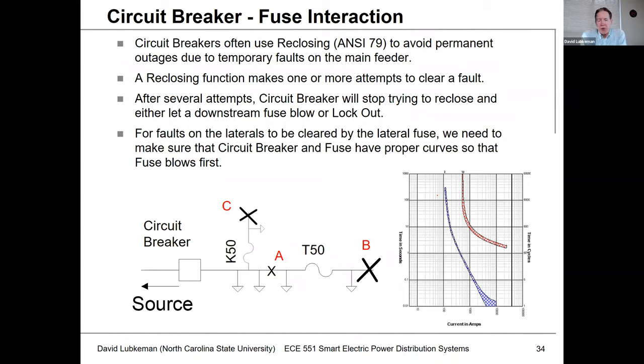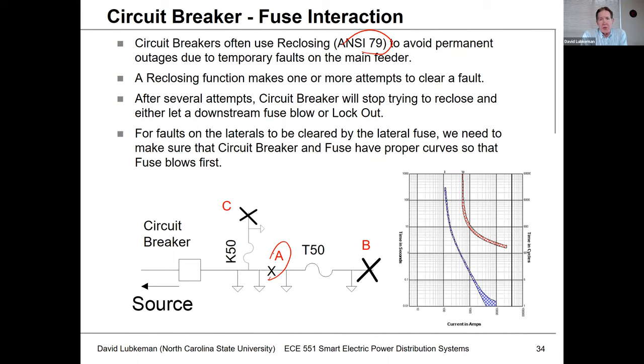For the interaction between circuit breakers and fuses, top-of-feeder circuit breakers are often set up to use reclosing — ANSI function 79. If we have a temporary fault on the main feeder, say at location A, we don't want to outage the entire feeder if reclosing could clear it. So we might give it one, two, three, or four reclosing attempts. If those attempts are unsuccessful, either a downstream fuse blows or the breaker clears the fault and locks out, requiring a crew or SCADA operator to close it back in.